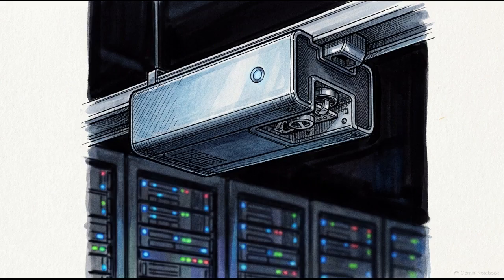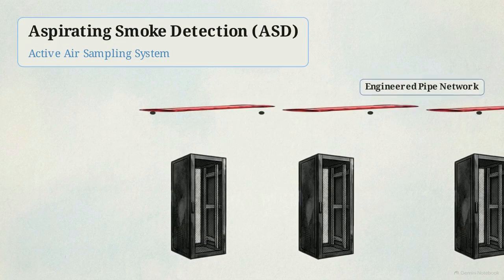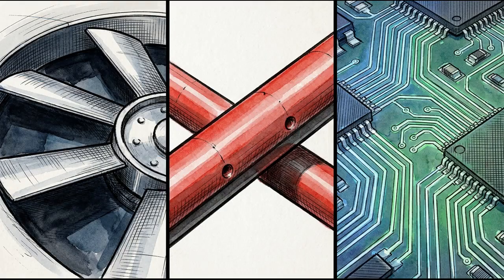These rooms require an active engineering solution. Aspirating smoke detection, or ASD, serves as the active countermeasure. It uses an engineered pipe network to physically pull air samples from specific pathways into a high-sensitivity sensing chamber. ASD represents a hybrid engineering discipline, integrating HVAC airflow, hydraulic pipe modeling, and digital logic.